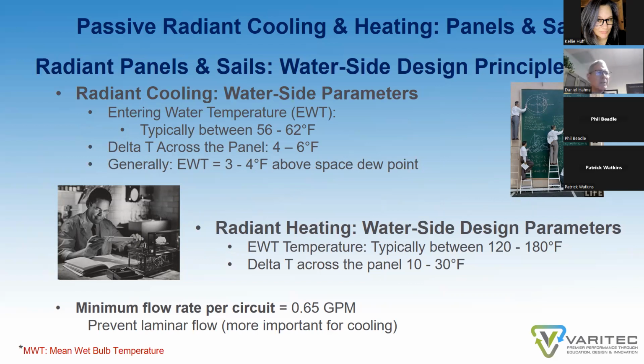Providing 56 to 62 degree chill water will give you about a 4 to 6 degree delta T of your chill water. That's quite a difference from the 20 degree delta T you need on an all air solution. You want to supply your entering water at 3 to 4 degrees above space dew point, because you don't want the panels or sails to condense. And that's easy enough to do, providing you have confidence in assigning the dew point temperatures to a space, which will be 55 degrees in a space designed to 75 degrees, 50% RH.